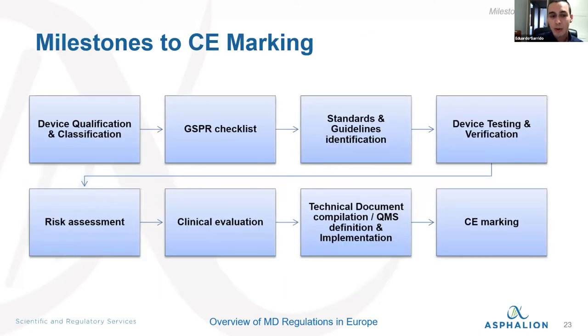So to recap, I'd like to make this slide with the milestones to CE marking, which is a process you should follow once you want to get your device to the market. So the first thing you should do is make certain your device is a medical device. Then once you know it's a medical device and it fulfills the requirements of the regulation definition, you have to classify the device according to the rules of Annex 8.